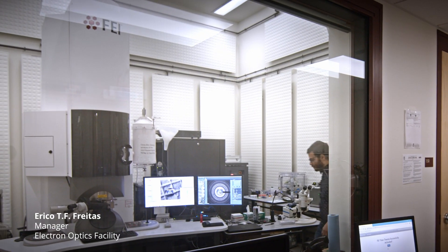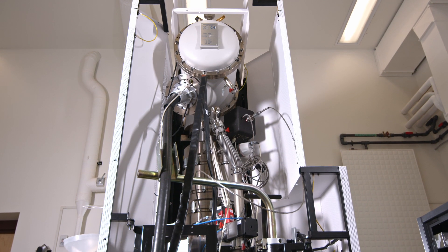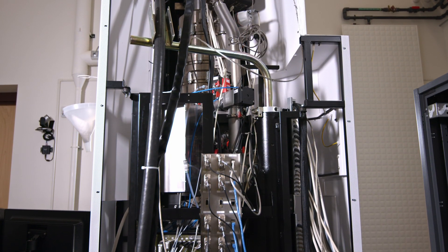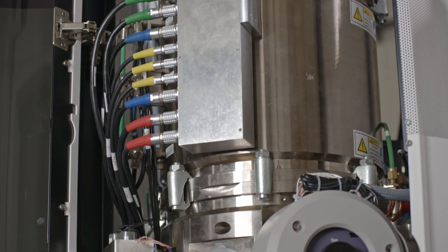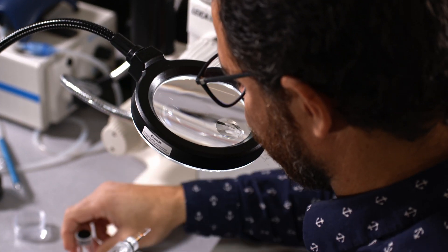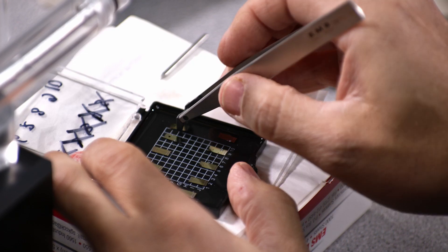In a specially constructed 900-square-foot facility, we stabilized temperature and movement to ensure successful operation of the FEI 200-kilovolt Titan Themis Scanning Transmission Electron Microscope, or STEM. One of only two Titans in the state of Michigan, it produces high-resolution images at atomic scale. A thin 3 mm specimen support disk is seated inside a larger holder, which is used to insert the specimen inside the microscope.